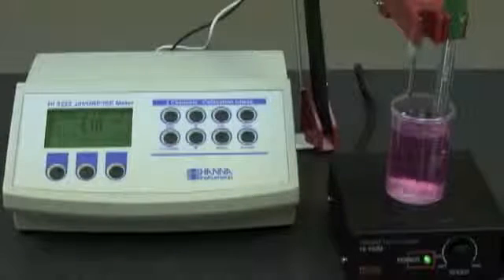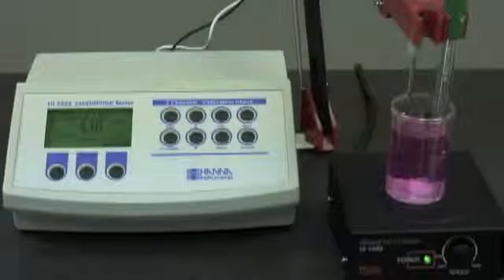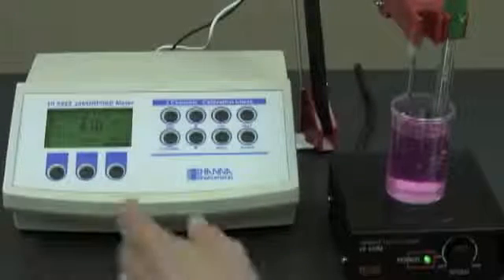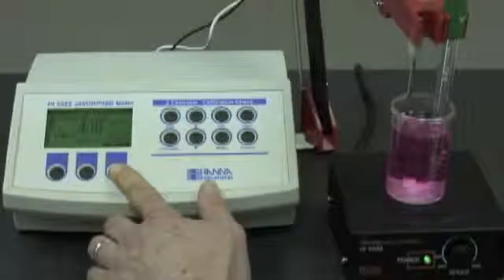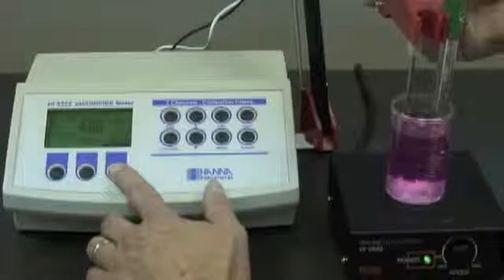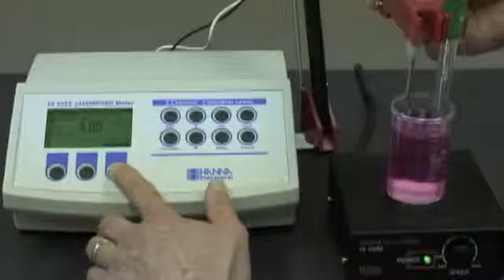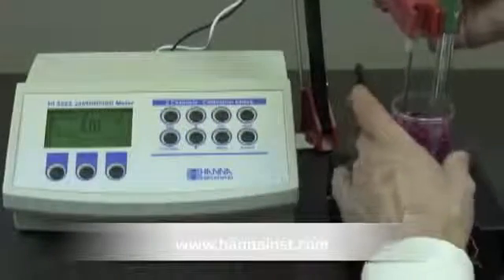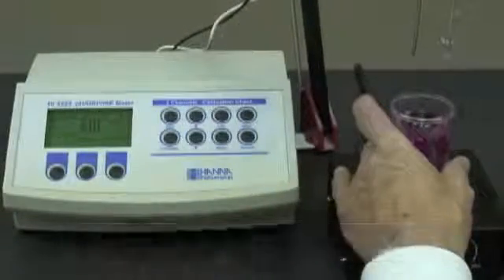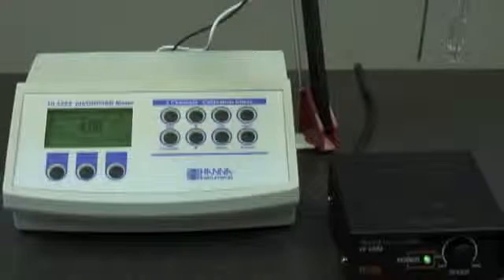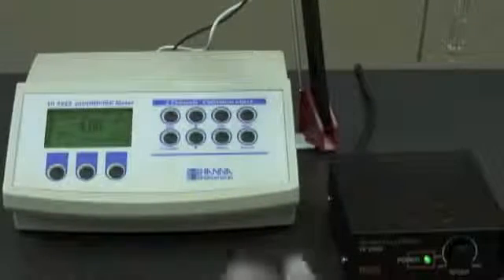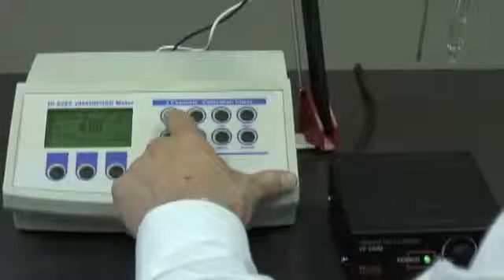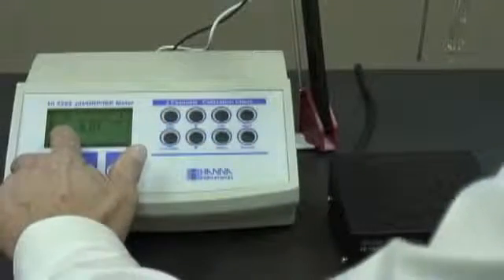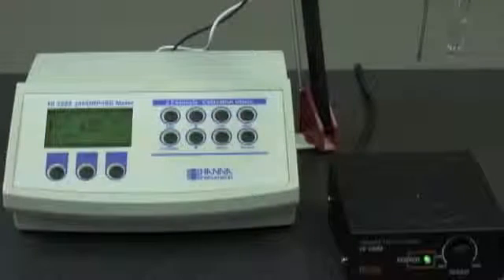Something important to note while this is doing its reading is that this meter has cal check. So if my buffer was contaminated or my probe was dirty, then the cal check feature would tell me that. So as you can see, I'm ready to confirm, and in this case, since I'm going to do just a 2-point calibration, I'm ready to take my measurement. But the next thing I'm going to do before I do that is escape out of here. And as you can see here, again, this is part of the cal check feature. This tells me that my probe is at 100% and it's ready to go after calibration.